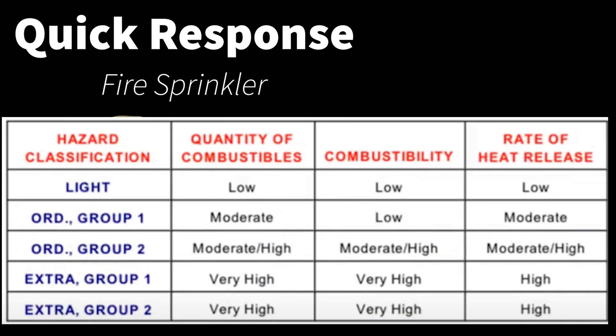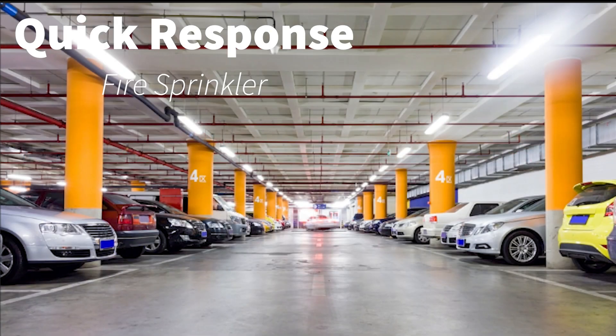When we move up to ordinary hazard, the combustible loads and rate of heat release starts to climb to moderate and high. In ordinary hazard, quick response is allowed when combustibility and rate of heat release is on the low to moderate side — for example, a parking garage. If the garage is a dry system, it will also benefit from the quick response's faster delivery time.